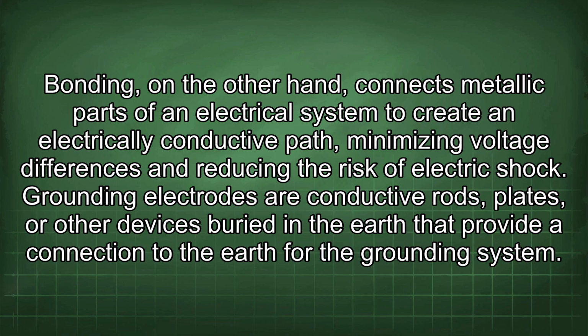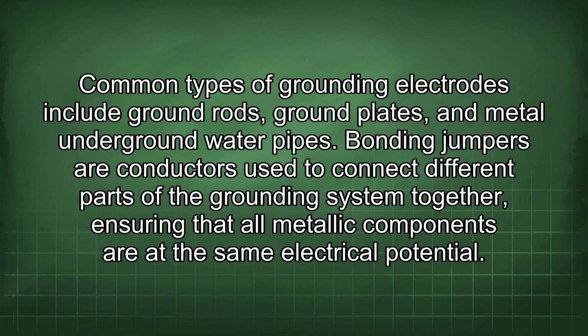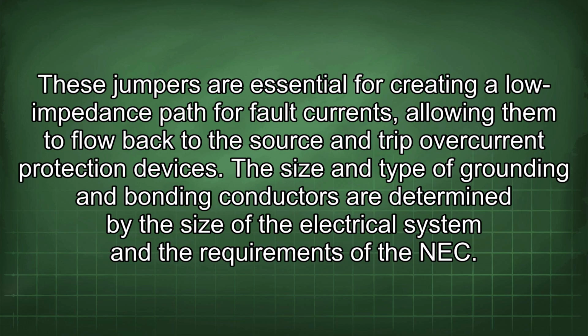Grounding electrodes are conductive rods, plates, or other devices buried in the earth that provide a connection to the earth for the grounding system. Common types of grounding electrodes include ground rods, ground plates, and metal underground water pipes. Bonding jumpers are conductors used to connect different parts of the grounding system together, ensuring that all metallic components are at the same electrical potential. These jumpers are essential for creating a low impedance path for fault currents, allowing them to flow back to the source and trip overcurrent protection devices.